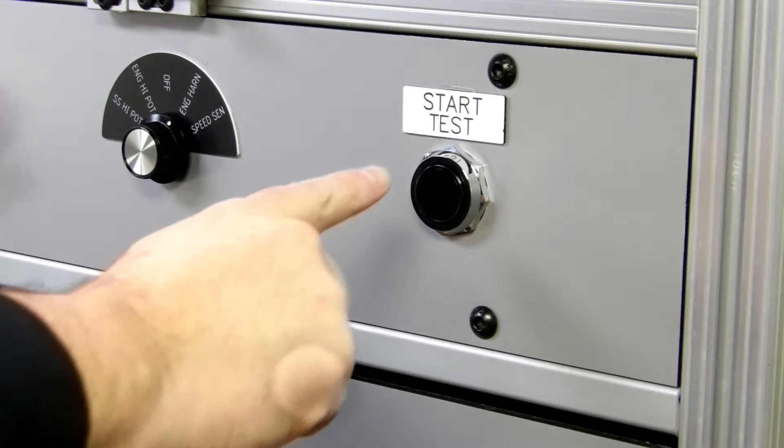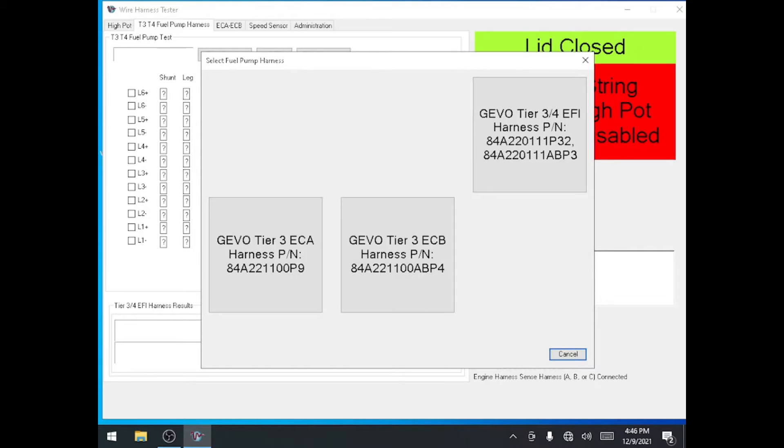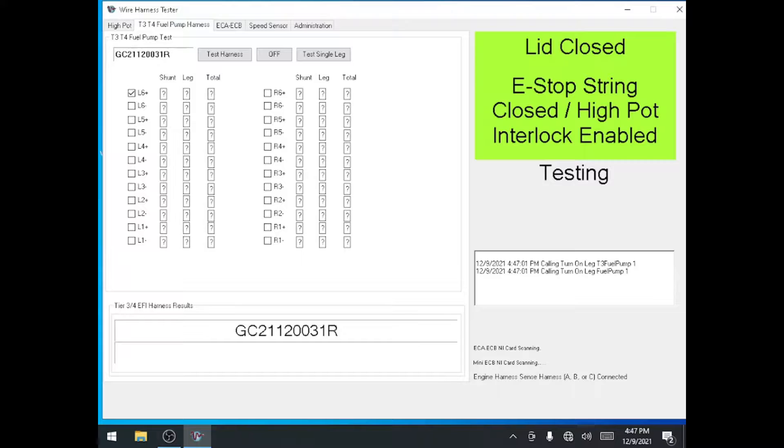Press the start button beside the selector switch to start a test. The software will ask which harness you want to test. Tap the EFI harness button on the test software screen. During the test, each wire will be tested for resistance to check for integrity.